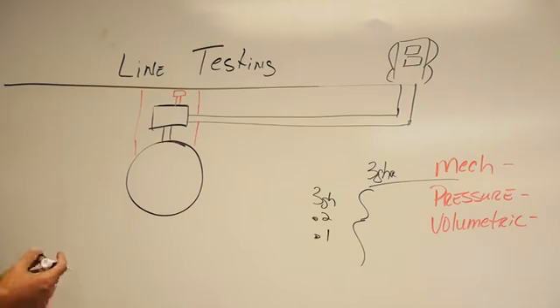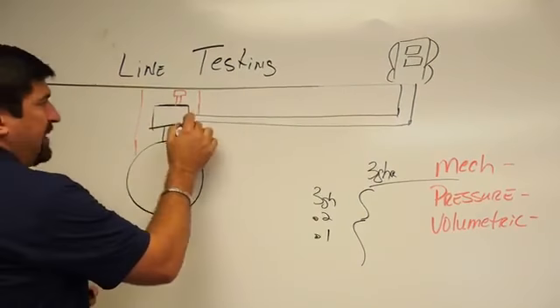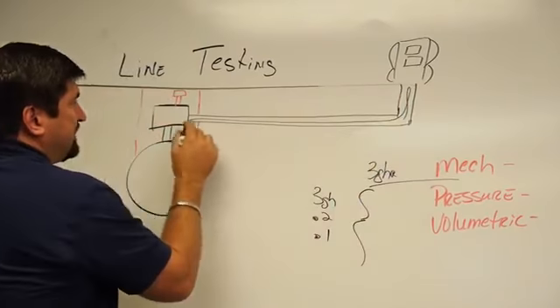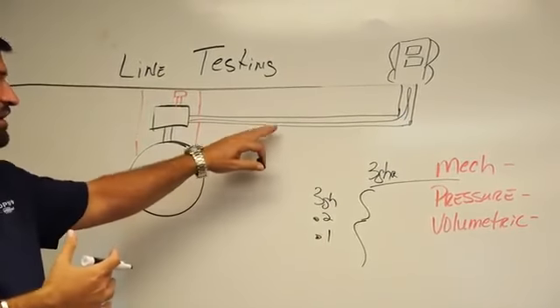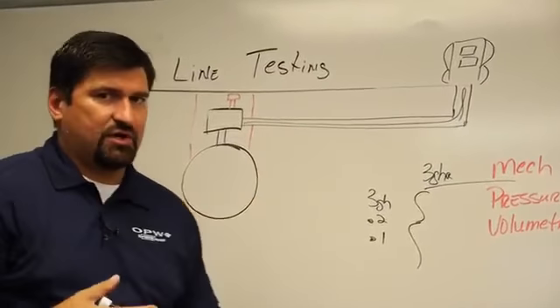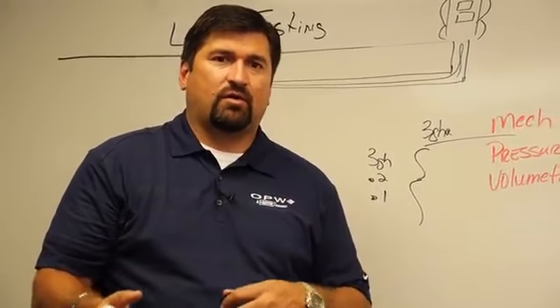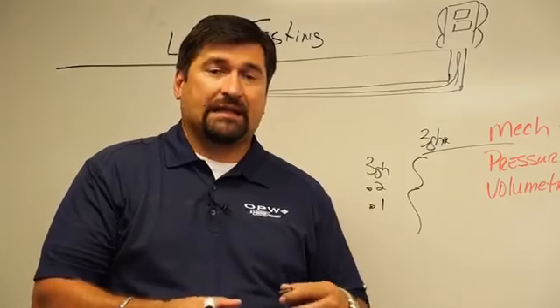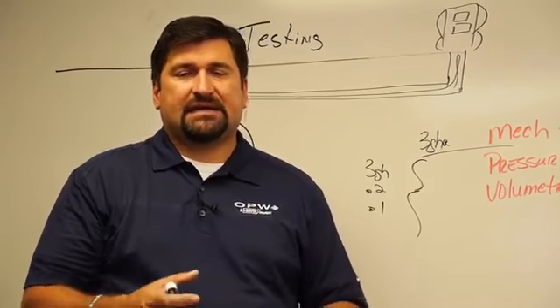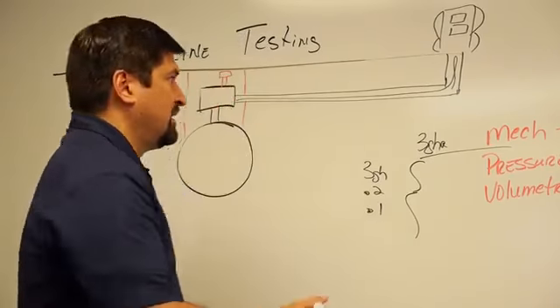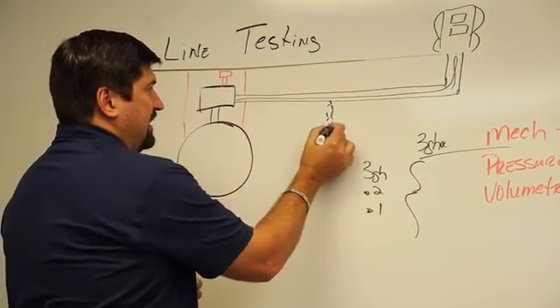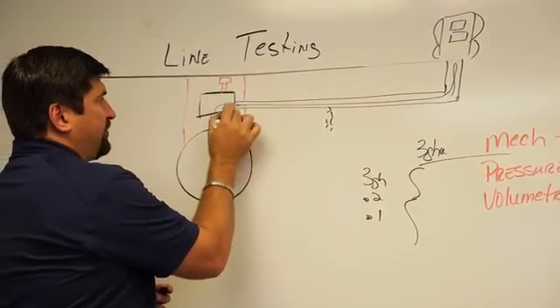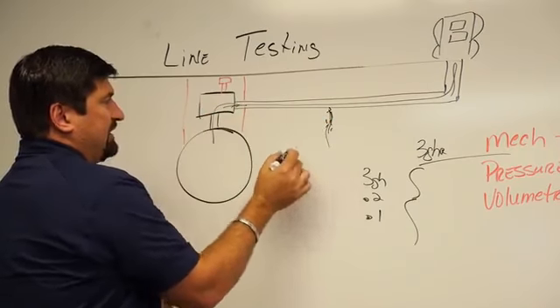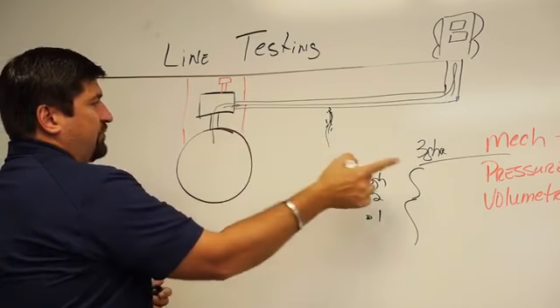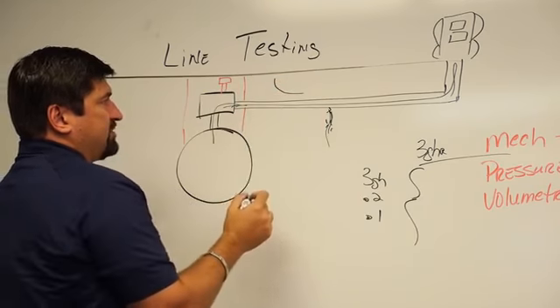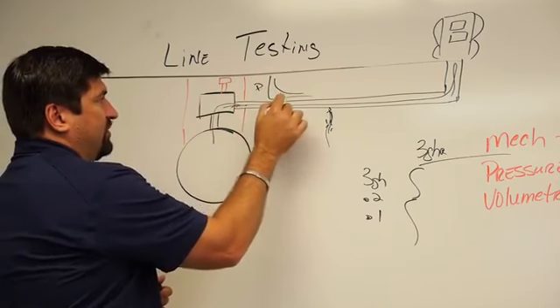Basically what they're doing is taking the motor and filling up the pipe with product, and they're looking to see if there's any pressure loss or volume loss within this pipe. Because you know that in a sealed cylinder, the only way that I can add product or liquid to a sealed cylinder is if the exact same amount of product is leaving that cylinder. So if I have a leak in this line, the only way that I can physically add product into this pipe is by that product leaving the line. In the PLLD or the pressurized piping, you will see a loss of pressure within that line if I looked at pressure over time.